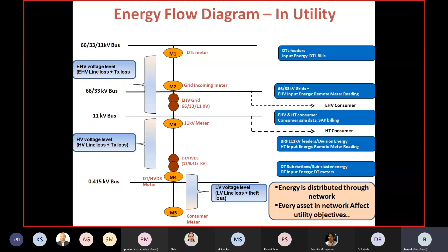Now all the assets in the network—energy flows through all of them, and their behavior, capacity, and capabilities affect the objectives of the distribution company. This is very important to understand. We normally say EHV assets have more importance, but no, each and every asset matters. When we talk about the distribution network, each asset—whether an LT feeder, a feeder pillar, or a distribution transformer—affects the utility objective in terms of capex, reliability, SAIDI, loss, and so on.